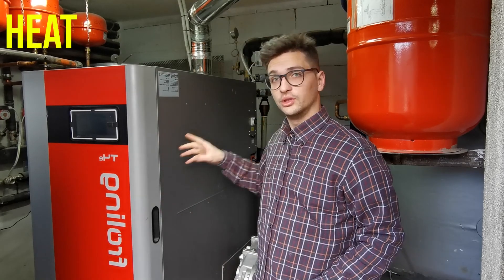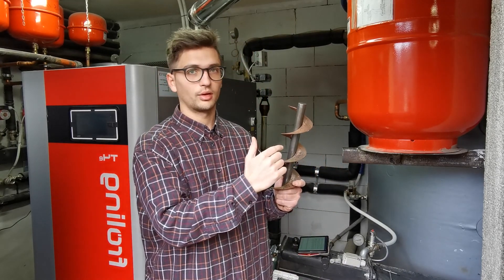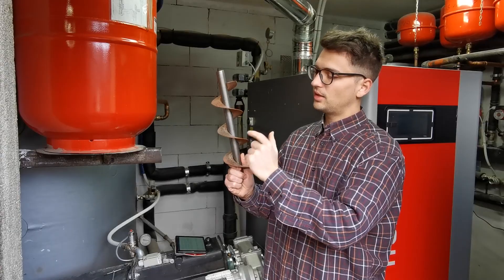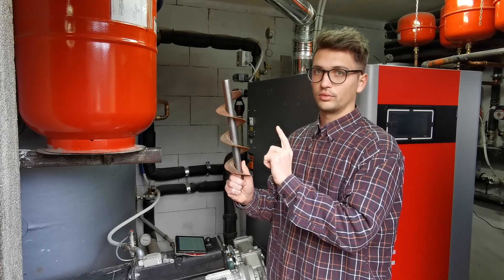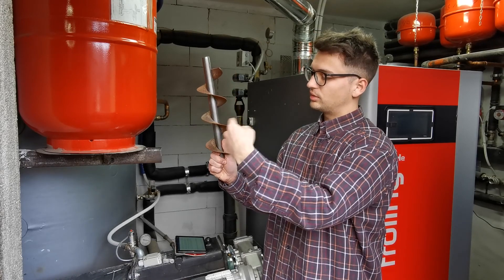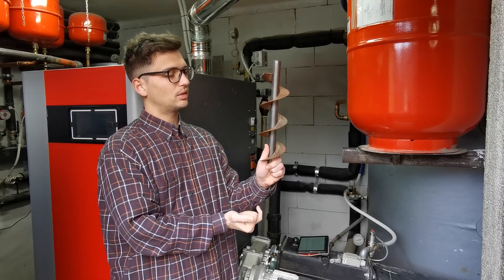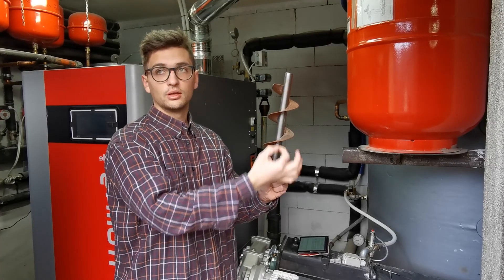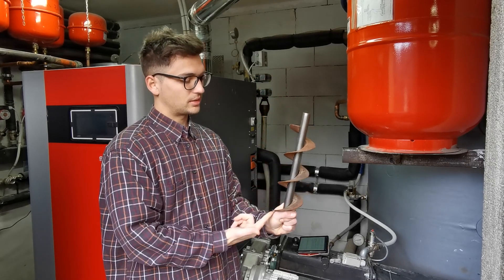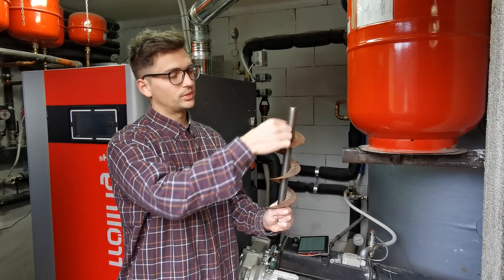In the upper part of the boiler, you have the heat exchanger. Cool water passes through pipes, and there are several lines of pipes. Inside the pipes, there are elements called turbulators — like steel screws. They serve two purposes: first, they introduce turbulences in the fumes flow, ensuring hot air is always in contact with the tubes; and second, since they slow down the speed of the air, flying ashes slow down and fall, effectively cleaning the air. The automatic cleaning procedure involves the turbulators moving up and then down, ensuring the tubes remain completely clean.